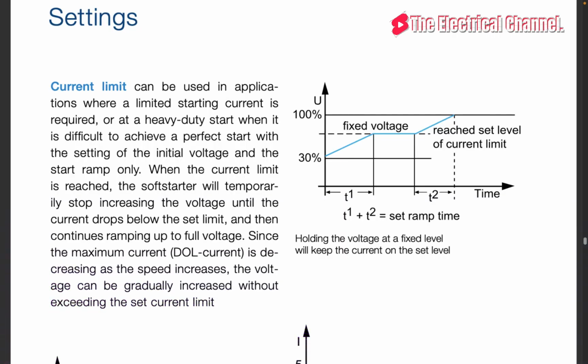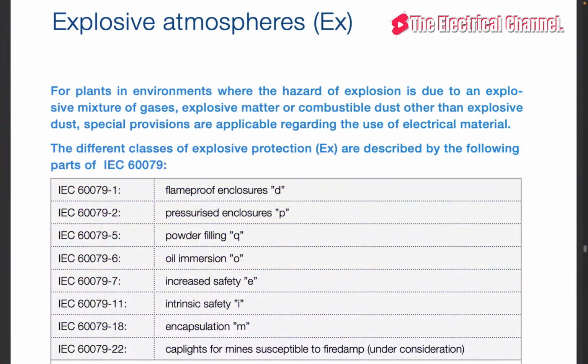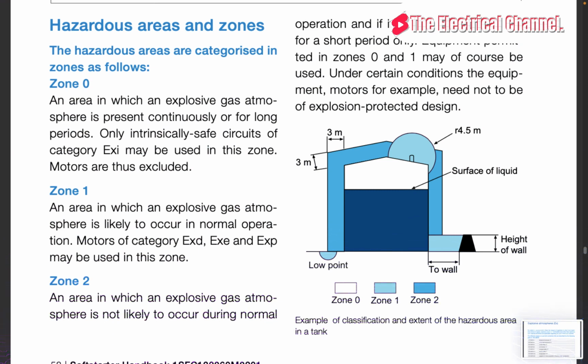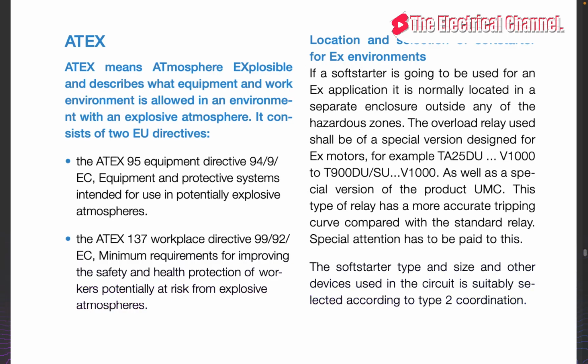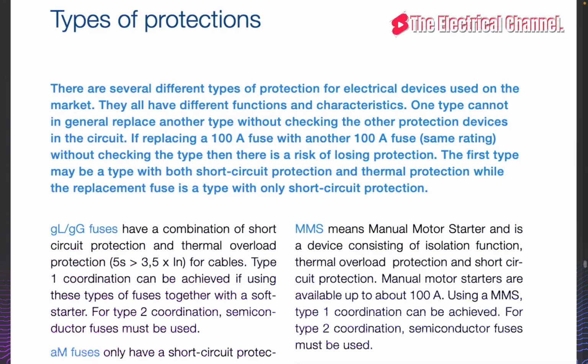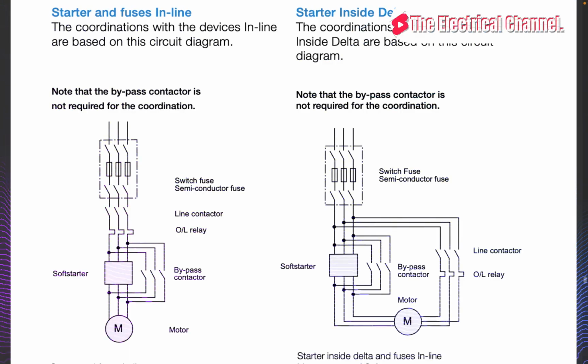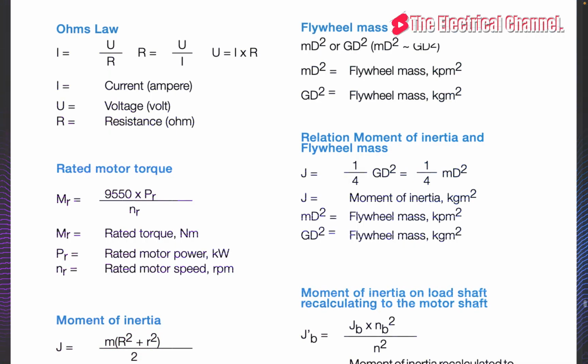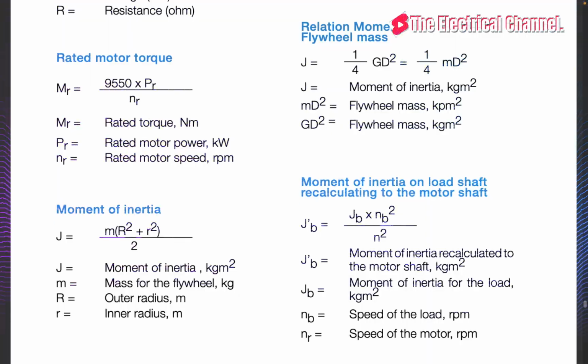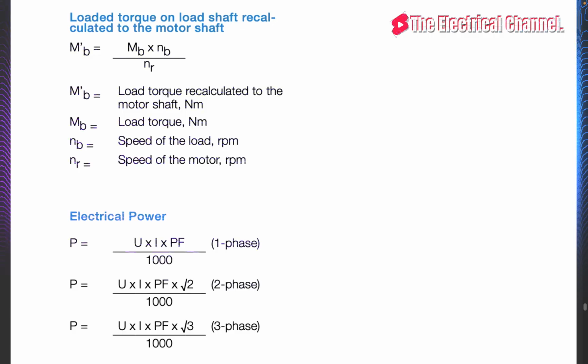However, as the voltage decreases, the current will instead increase. This is because the motor will try to remain in its current state. Since torque depends on both the voltage and the current, it will remain more or less unchanged. Then, after some time, when the voltage has dropped enough, there will be a sudden drop in current and the torque, and the motor will stop suddenly. This stop will still be far better than a direct stop, but in many pump systems this is not good enough. So another solution must be found.